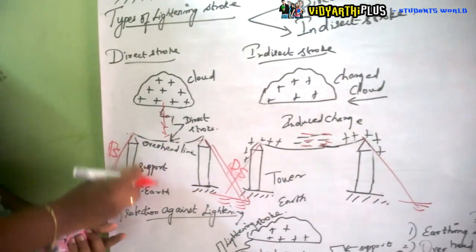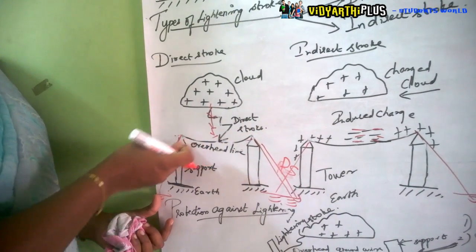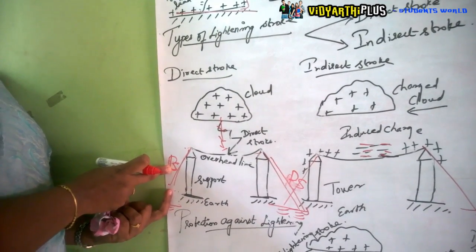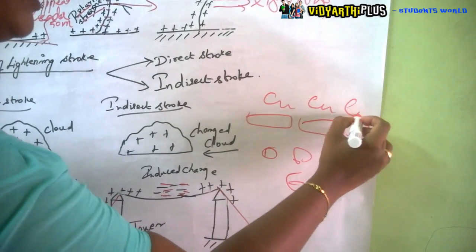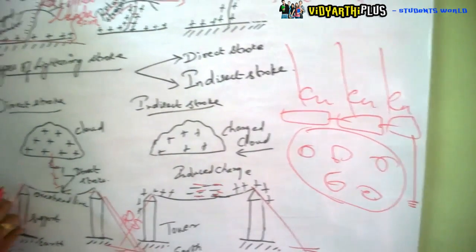The first method is the earthing screen. Since the tower is connected to power system components, any lightning charges reaching the overhead line would affect all components. To protect them, copper conductors are placed above the components. These copper conductors are interconnected and connected to the ground, so all lightning charges are absorbed by the copper conductors and directed to earth, completely protecting the power system components.